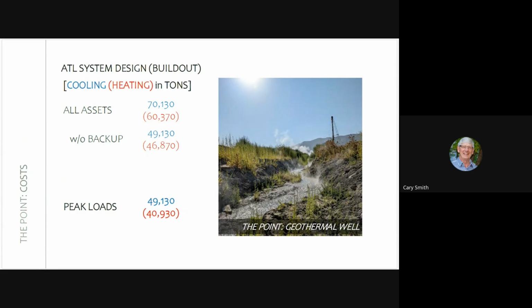Anyway, if we look at it, the peak loads were roughly 49,000 tons in cooling and 40,000 tons in heating. We looked at combining all those renewable assets together, and putting in a backup, which would probably be natural gas and cooling towers. And the cooling towers, by the way, are water consumptive, but we would reduce them, and we would have about 70,000 tons of utility available to us. And if I just use the resources which were renewable, that list of resources I gave you, I actually can cover the entire load of this project, 49,000 tons of heating and cooling.